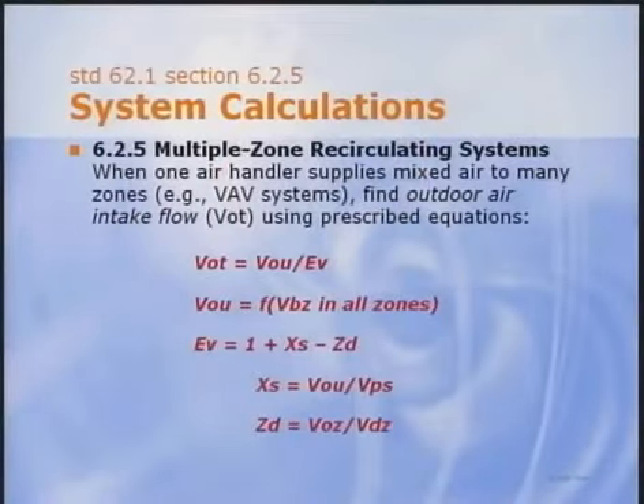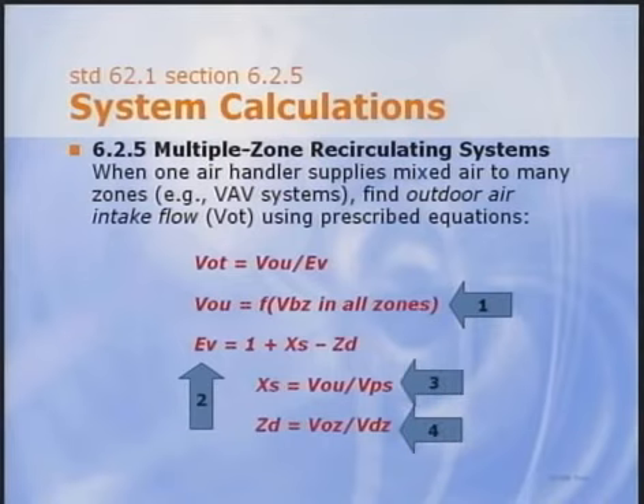Standard 62 recognizes this characteristic of multiple zone systems and requires designers to account for it. As these multiple zone equations show, the intake airflow at the air handler depends on the outdoor air needed in all breathing zones and the system ventilation efficiency, which according to Appendix A depends on the system primary airflow and the current discharge airflow to the critical zone. In VAV systems, both zone and central fan primary airflow change at part load. So even with constant population, these airflow changes result in variations in efficiency and required intake airflow. With this in mind, one way to dynamically reset outdoor airflow in VAV systems with DDC controls is to respond to ongoing efficiency changes. This is what ventilation reset control does.